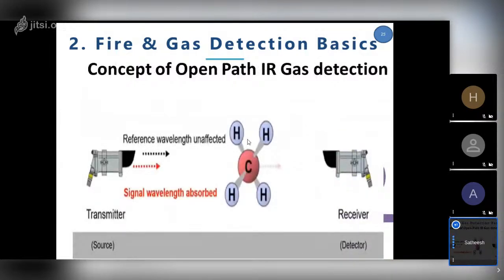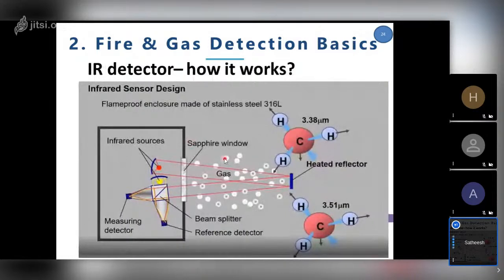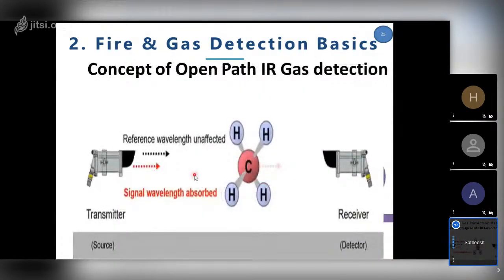Now comes the open path gas detector. Here, the same scenario, infrared absorption, but you see a transmitter and a receiver. These are kept apart. In the previous slide, I showed you how the whole thing is in one equipment, which is hardly 3 centimeters inside the instrument. Whereas here, as I explained before, it can be 5 meters to 200 meters, and in between nothing, absolutely nothing. So imagine there is a process equipment here, and you are living somewhere here, like an office building, and you want to protect against the gas coming over there.